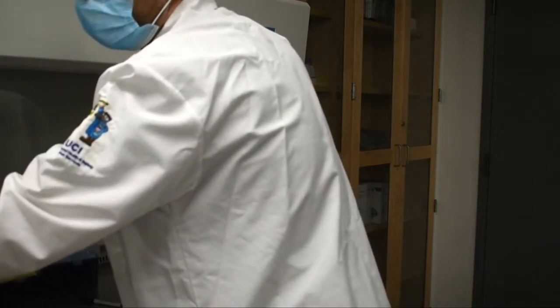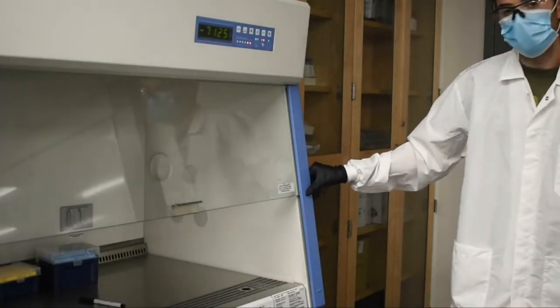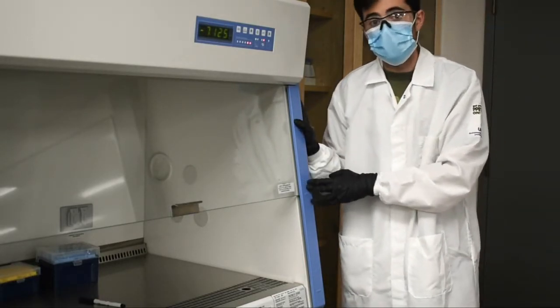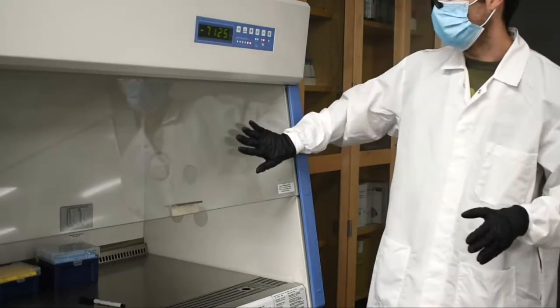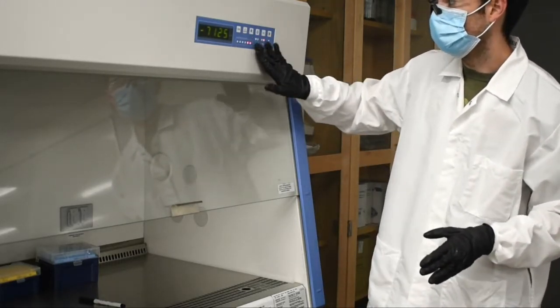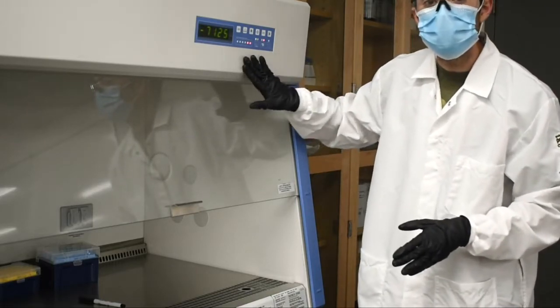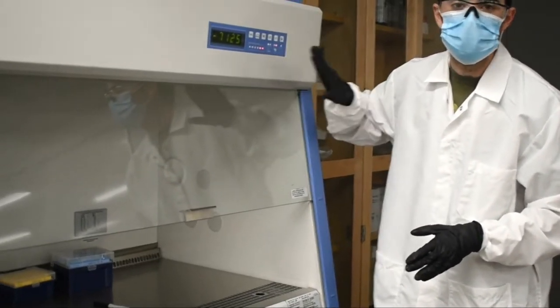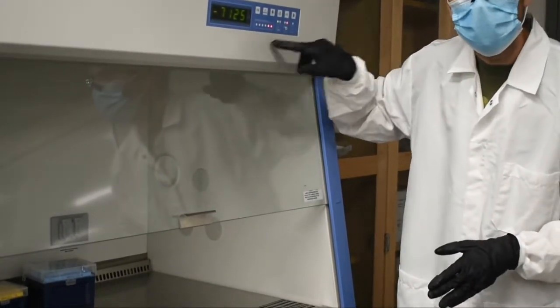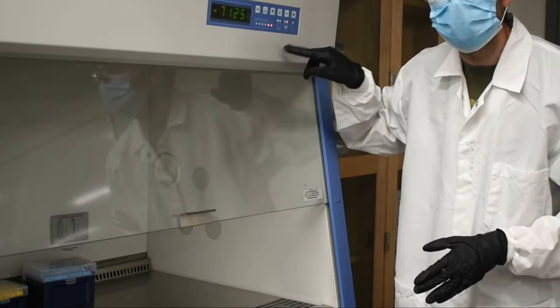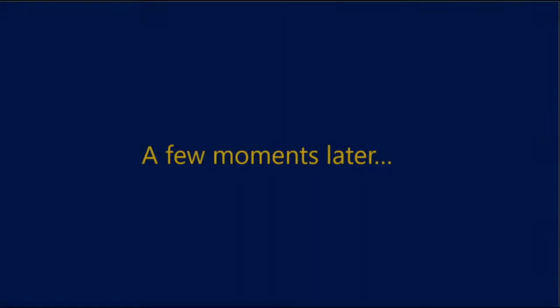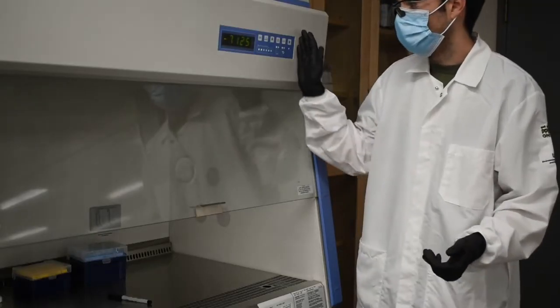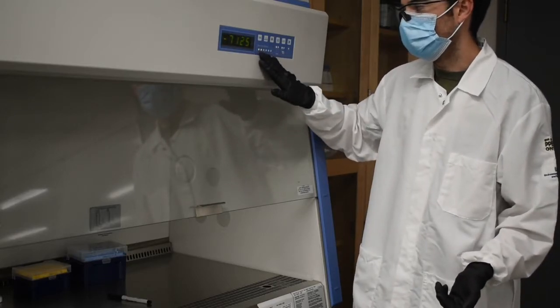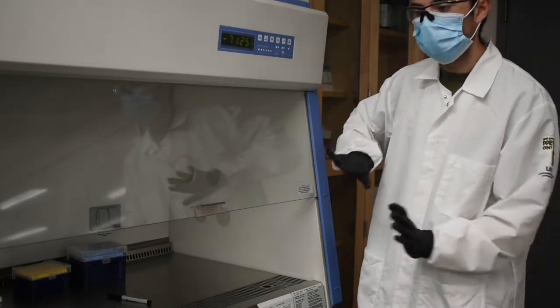And as I open the hood, you'll start to hear an alarm. That's letting you know that the machine's turning on. And as I said before, now the machine is on, and what's nice is before working in it, you need to wait till these smart flow indicators turn green. That's what indicates that it's safe to work in this space and that the airflow is established. If it is not established, you do not want to be working in the Biosafety Cabinet until it's completed. That we have established our safe airflow as indicated by here, all the dots are green. That means we can now start putting things into the hood.